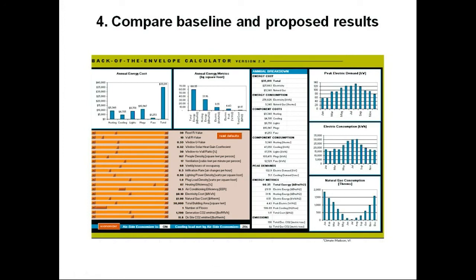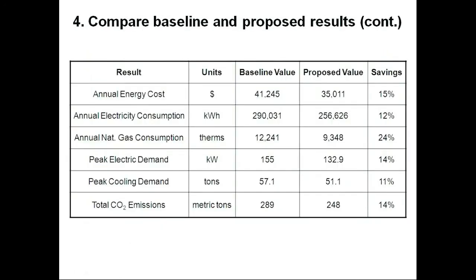We can also compare — not just qualitatively but quantitatively — the same results between the proposed and baseline cases. This table illustrates the baseline and proposed values for the annual energy cost. We have a decrease of 15%, or about $6,200 in savings from our host of measures. Annual energy consumption is reduced by 12%, and natural gas by 24%. So our measures affected natural gas consumption much more than electricity consumption, which is important in a cool climate like Madison. Our peak electric demand and peak cooling demand have both decreased, which could result in reducing the overall cost of initial equipment. And finally, our annual CO2 emissions have decreased by 41 metric tons.